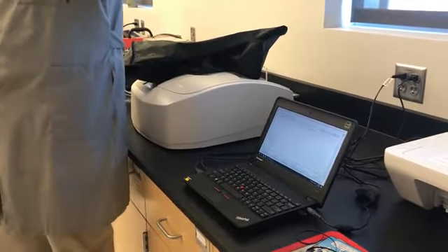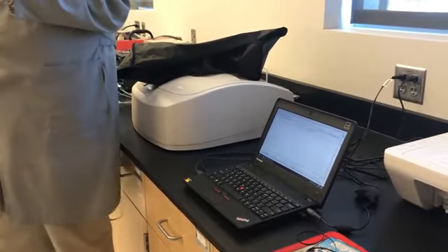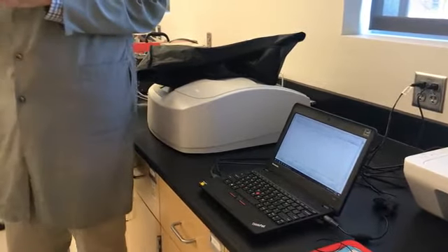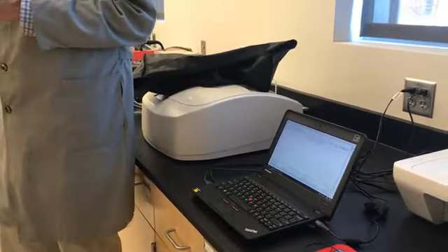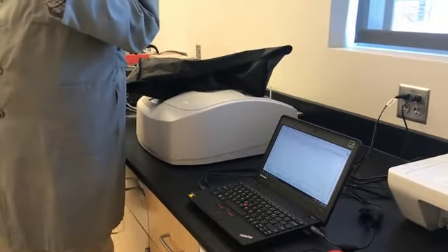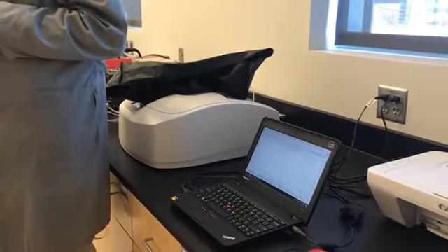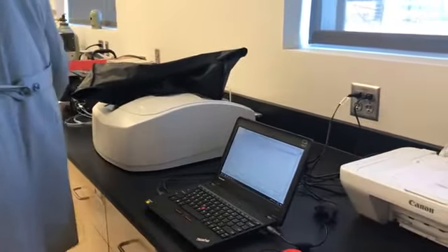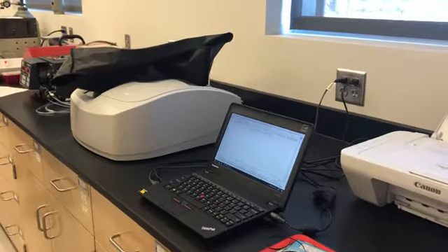There's carbon dioxide in the air, there's water vapor in the air, and those will actually absorb. So we record the background scan, and then we subtract out those absorptions due to the water vapor and the carbon dioxide. Okay?